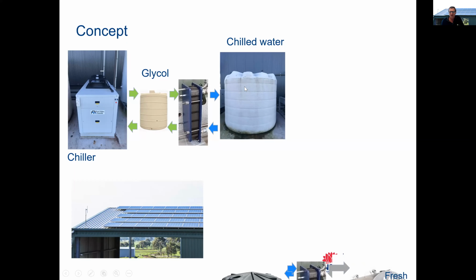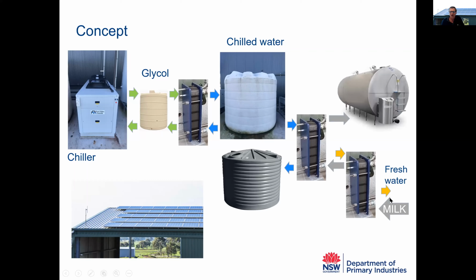This all happens outside milking times. During milking, when the milk comes in through your first plate cooler, rather than going into the vat at around 20 to 24 degrees, it goes through a second plate cooler and is chilled by the chilled water, going into the vat at sort of 6 to 8 degrees. So we're using this cheap stored energy to reduce our energy use in the vat.